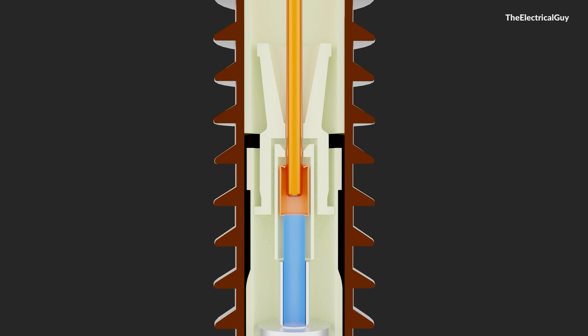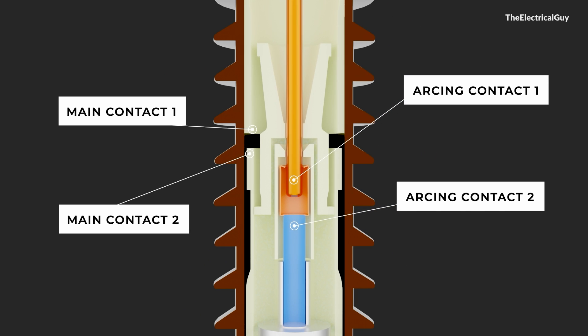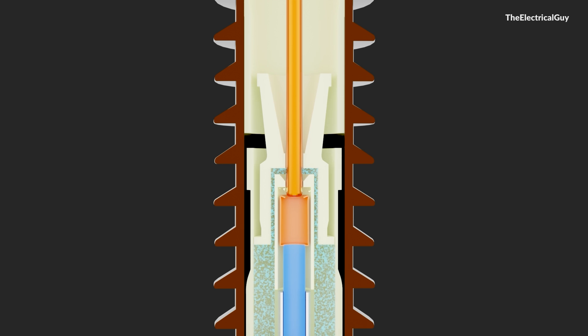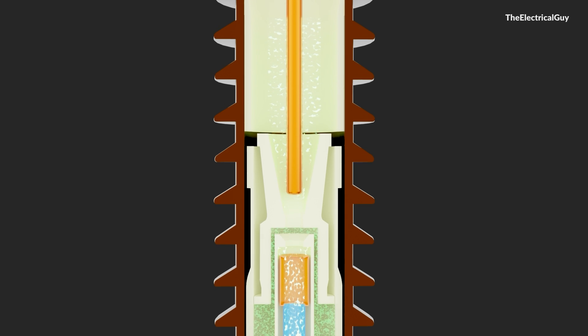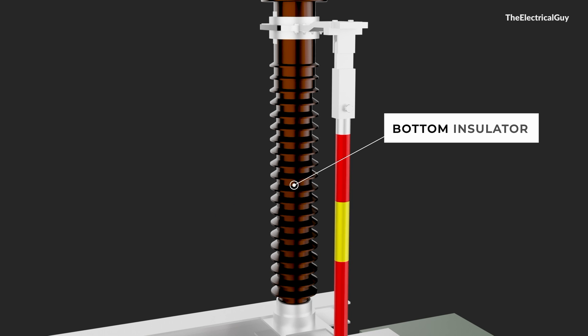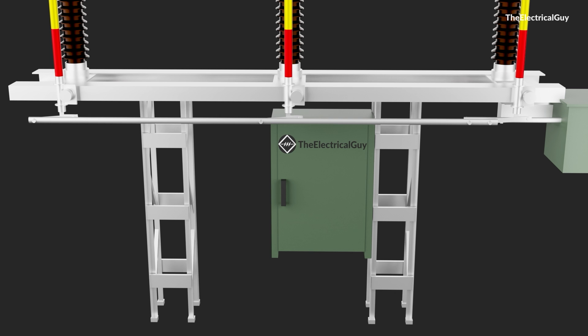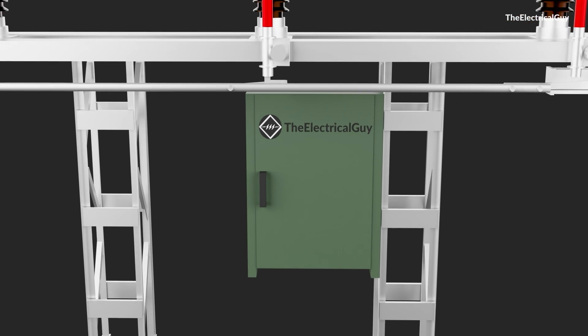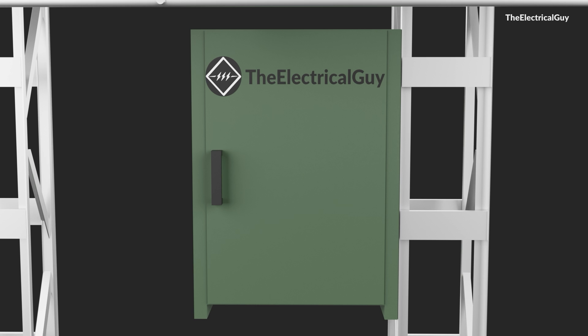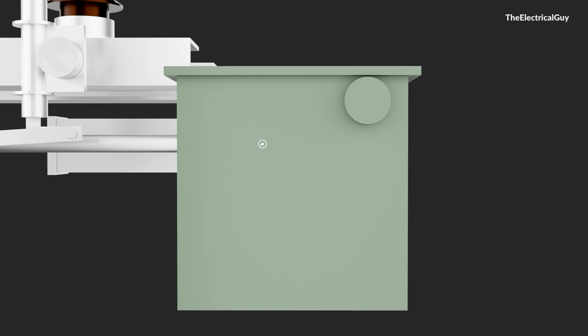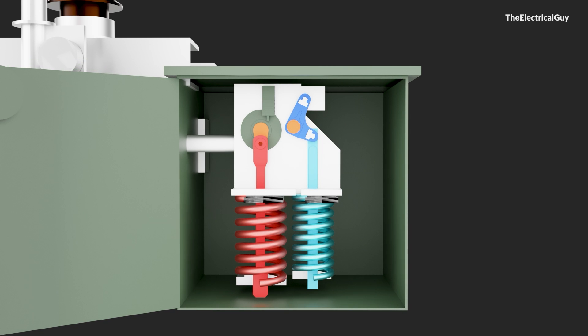Construction-wise there is no major difference. The contact system remains the same: the main contact and the arcing contact. To achieve the isolating distance, the distance between the contacts may or may not be increased depending on the design and type testing results. The bottom insulator is the support insulator required to maintain safe clearances, and then we have the support structure and the operating mechanism. Since we are providing an integrated earthing switch, a dedicated earthing mechanism is also needed to operate it, which you can see here. Let us have a look at how the operation happens.